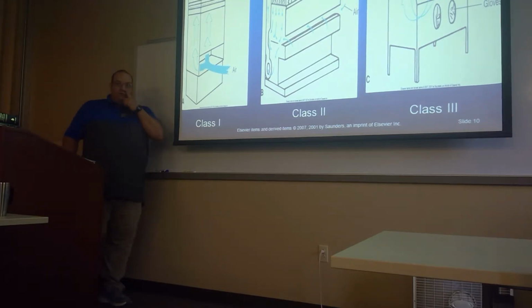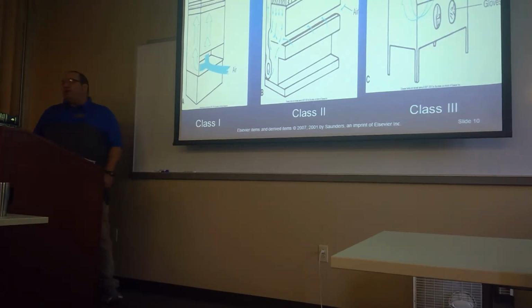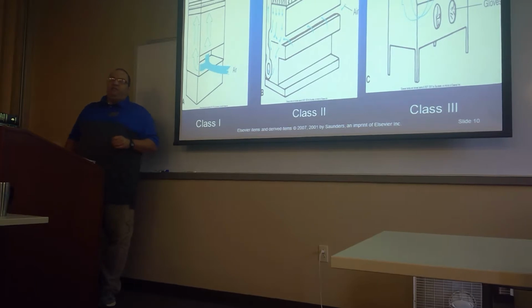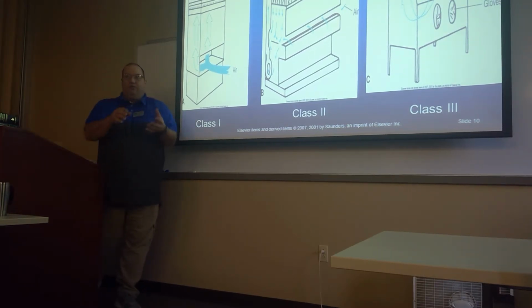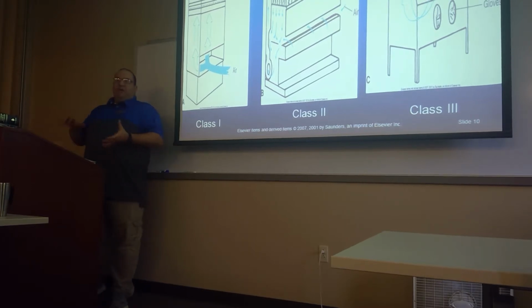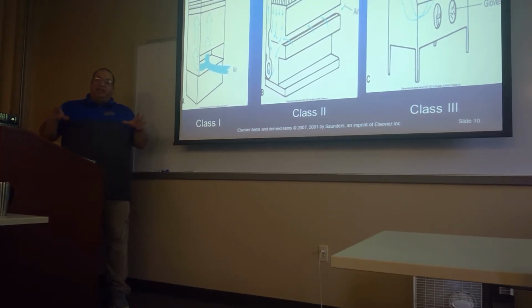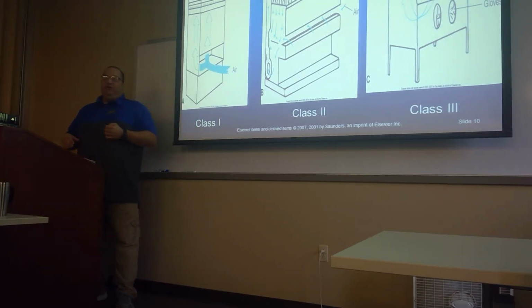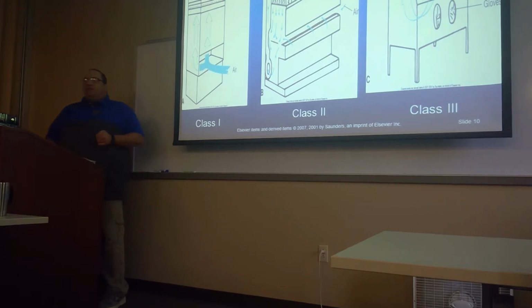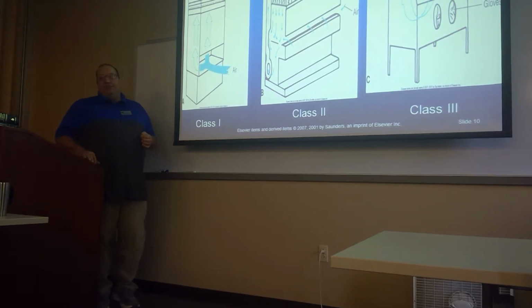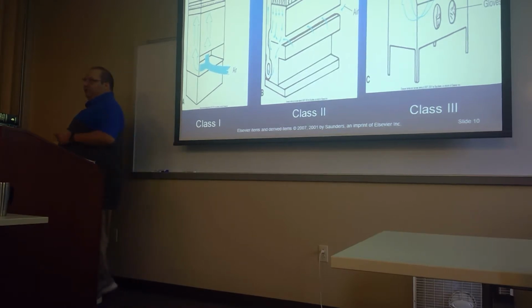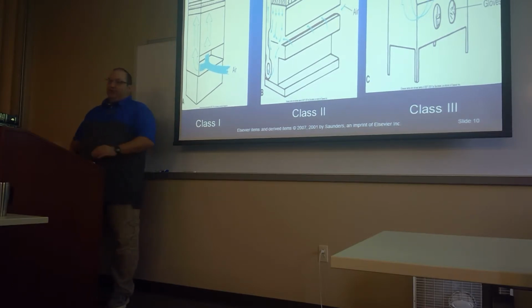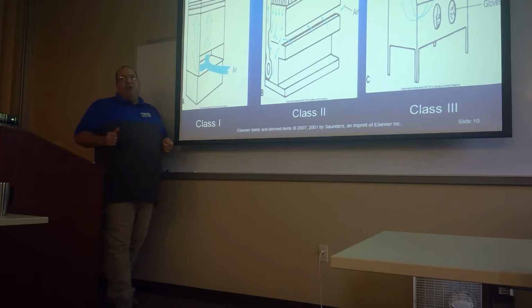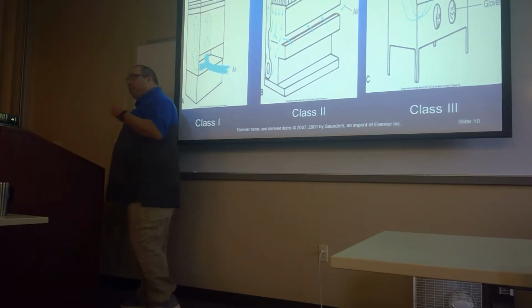Class 3 you don't see in hospitals. You'll see this at places like the state health department or the CDC. It's completely enclosed, the kind you see on TV where they stick their arms through rubber gloves to work, never directly exposed. It comes in a sealed container, you put the container inside the hood, then reach in and open it there, never exposed to it. When they work with things like Ebola, tuberculosis, or anthrax, this is the type of hood they use; they're never exposed to it. You won't see that in hospitals, you'll see Class 2s there. Class 1 is something you might see in a high school or college biology lab, the bare minimum of safety.